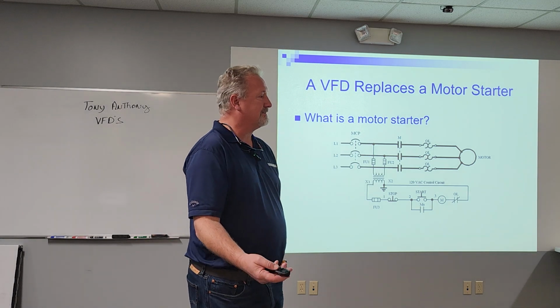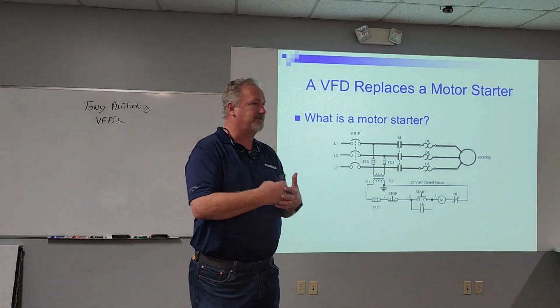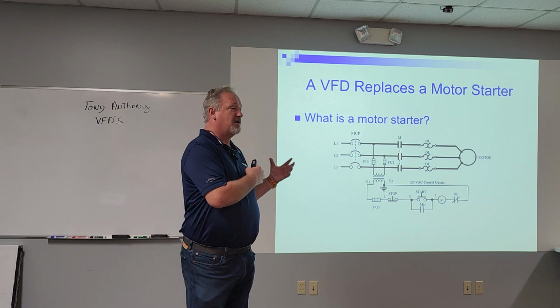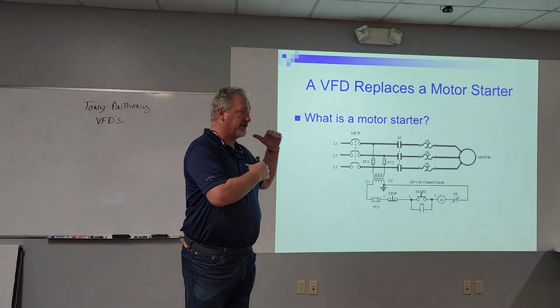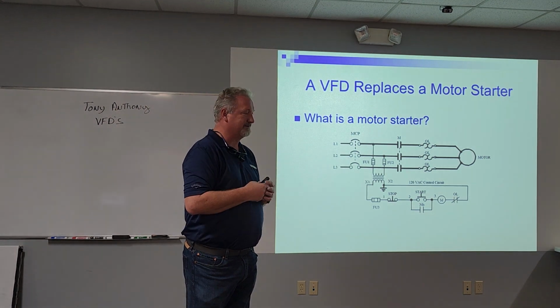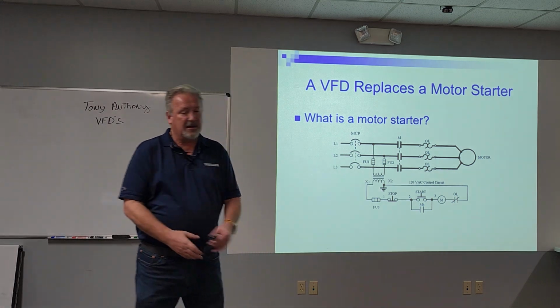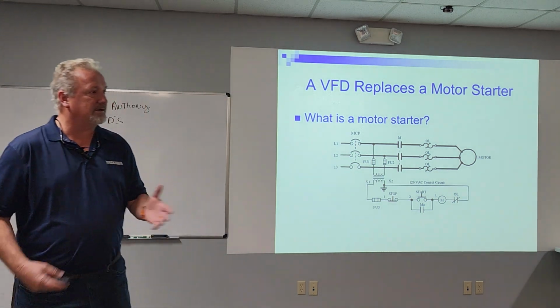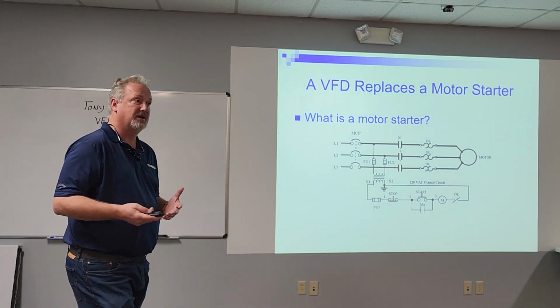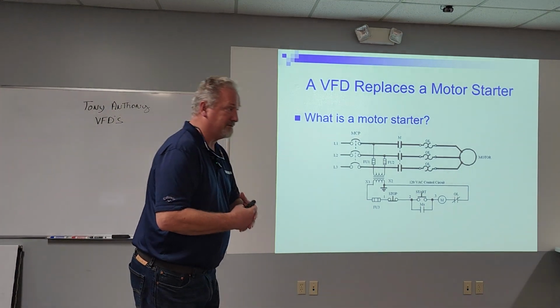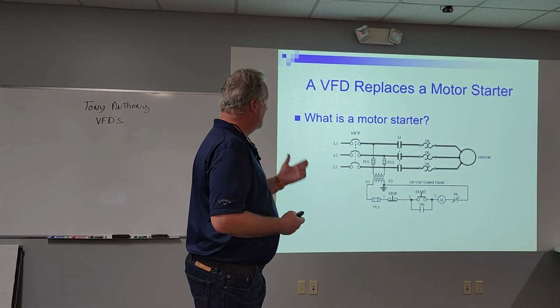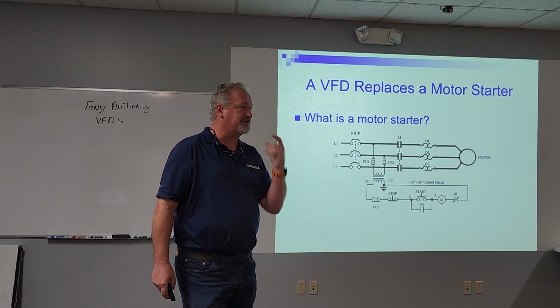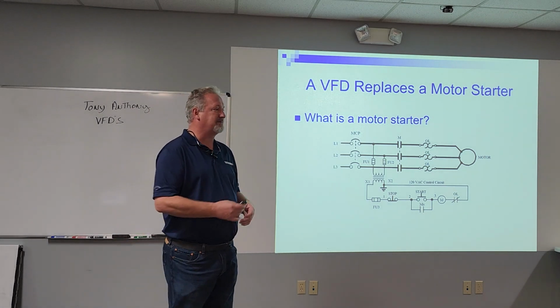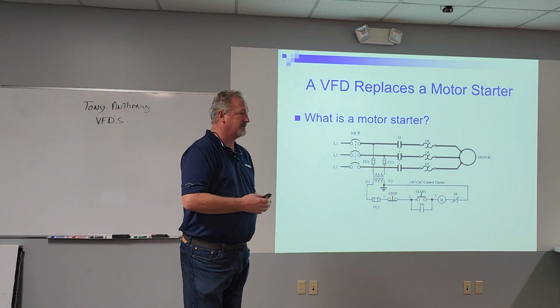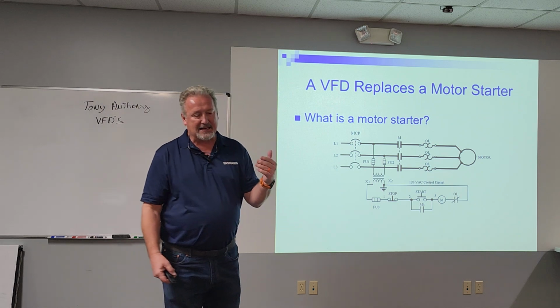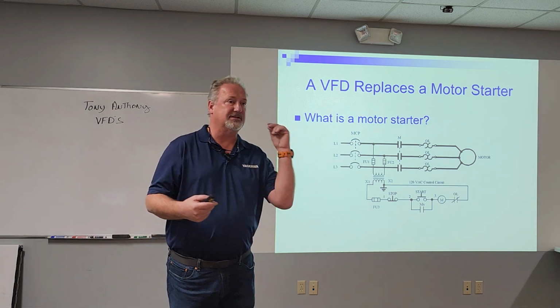Everybody knows what a motor starter is, right? You got basically a set of contacts that pull in and instantaneously run that motor from 0 to 60 hertz within just a split second. Problem with motor starters is, 1, you can't control the process. 2, you're using full energy. But 3, every time you start that motor, you'll get 6 to 8 times full load amp inrush current. So if you got a 100 amp motor, that's 600 to 800 amps for a split second.